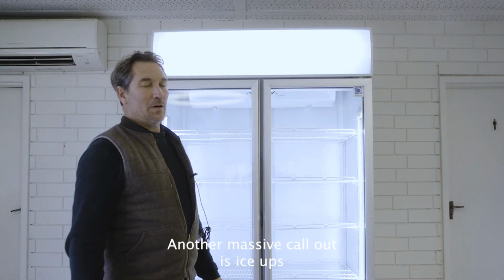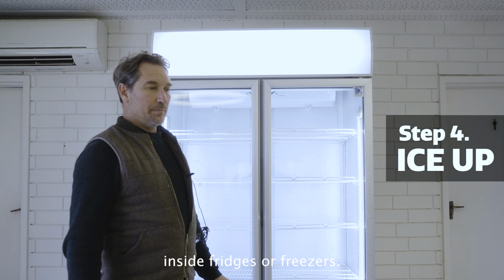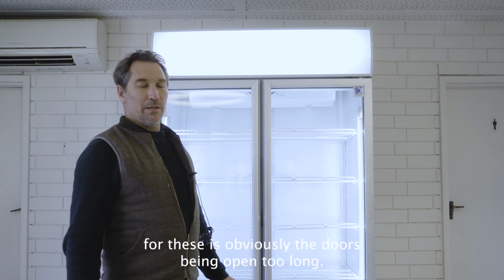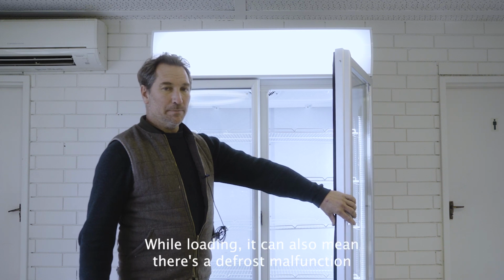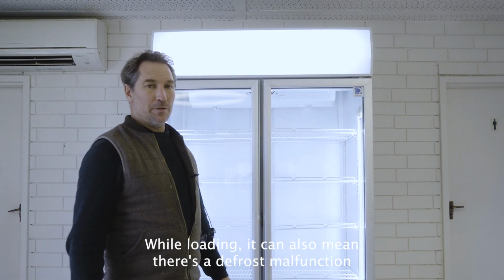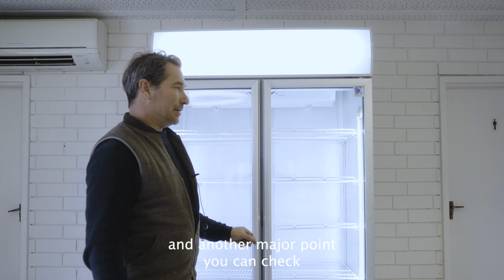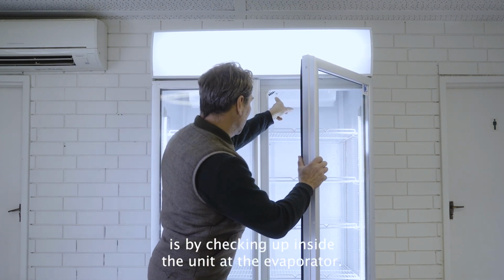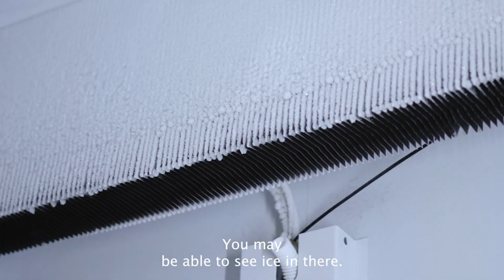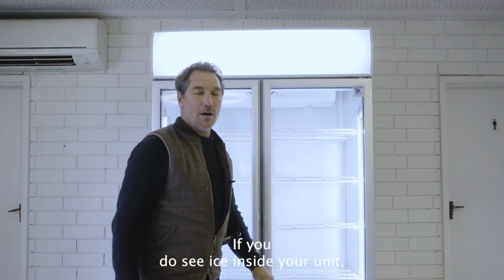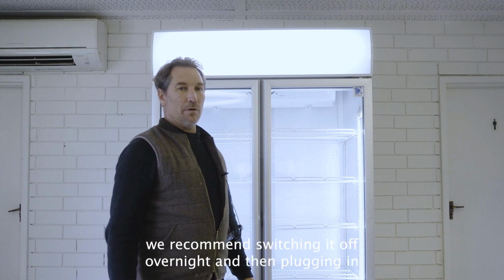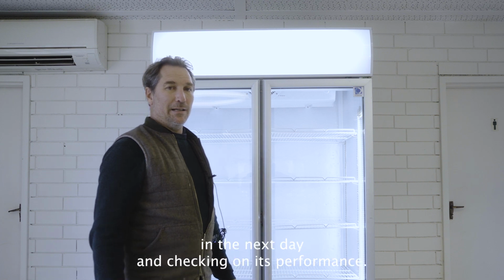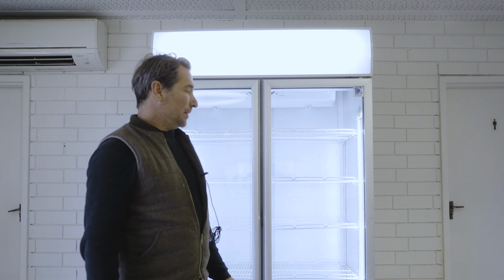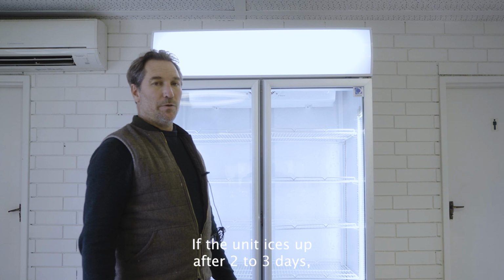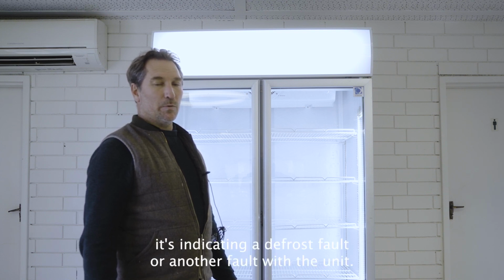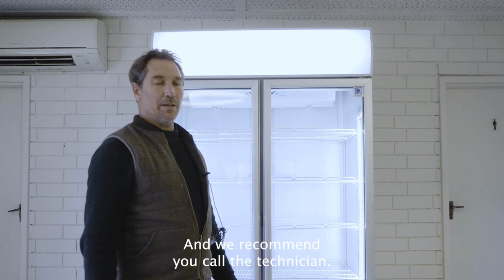Another massive call out is ice ups inside fridges or freezers. The first cause for these is obviously the doors being open too long while loading. It can also mean there's a defrost malfunction. And another major point you can check is by looking up inside the unit at the evaporator, you may be able to see ice in there. If you do see ice inside your unit, we recommend switching it off overnight and then plugging it in the next day and checking on its performance. If the unit ices up after 2 to 3 days, it's indicating a defrost fault or another fault with the unit, and we recommend you call a technician.